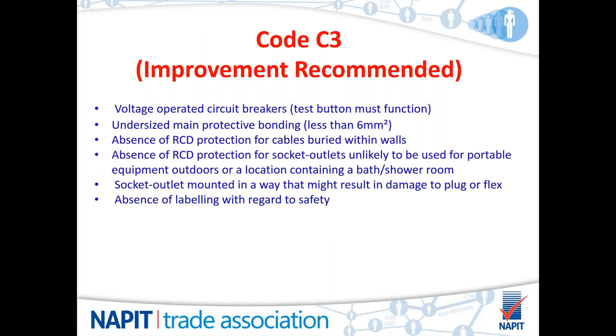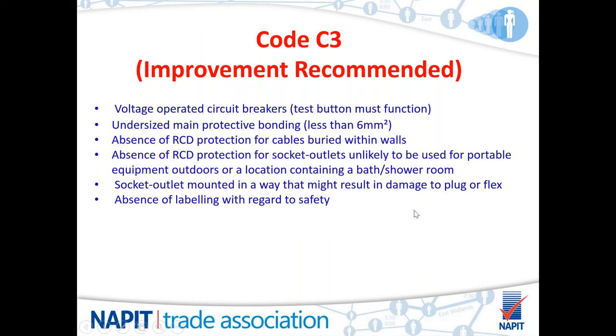Absence of RCD protection for sockets which are unlikely to be used for portable equipment outdoors, then again, as long as they aren't used outdoors, as long as they aren't in a bathroom or a shower room, any place containing a bath or shower, then C3. A socket outlet mounted in a way that might result in damage to the plug or socket arrangement, C3, unless you can see damage to the flex already. And any absence of labelling, your periodic inspection labels, your safety electrical connection, do not remove labels on BS 951 earth clamps. It doesn't take away any of the safety, but an improvement should be recommended.